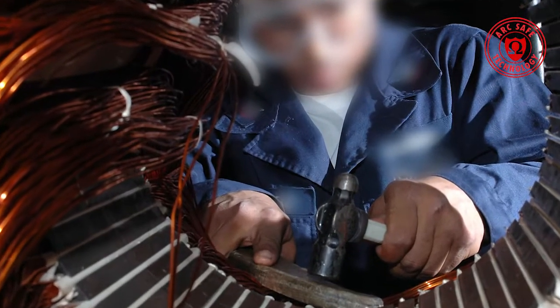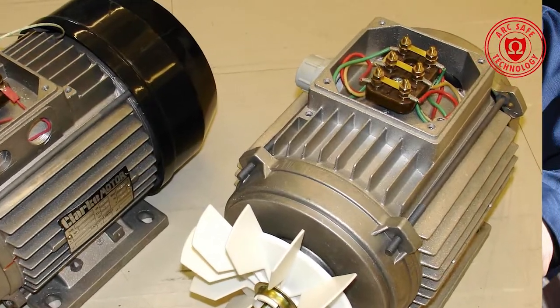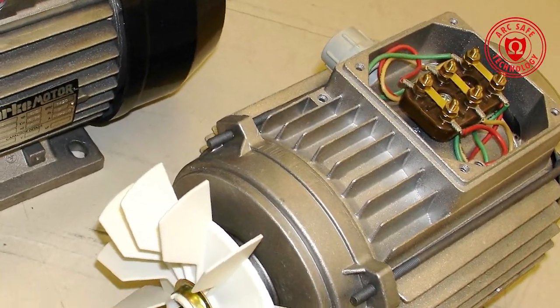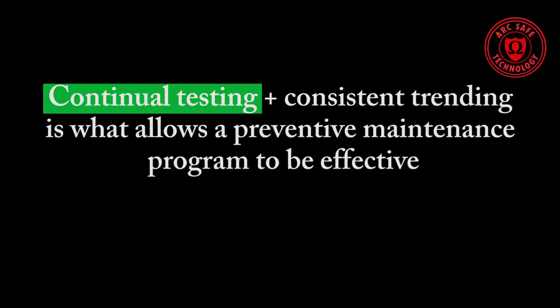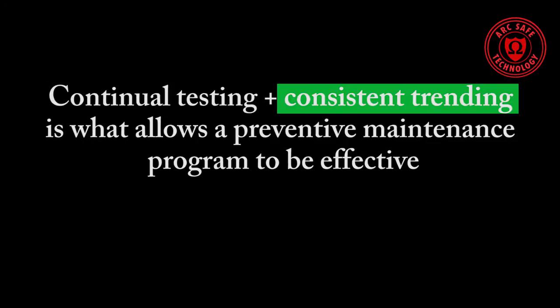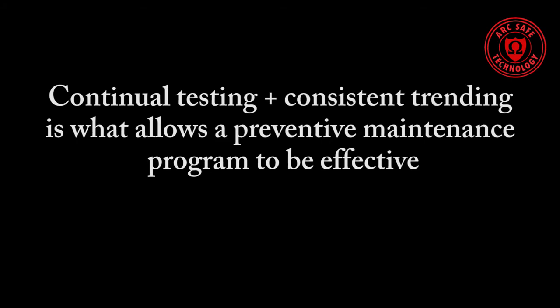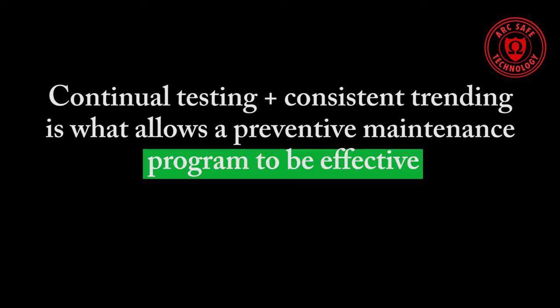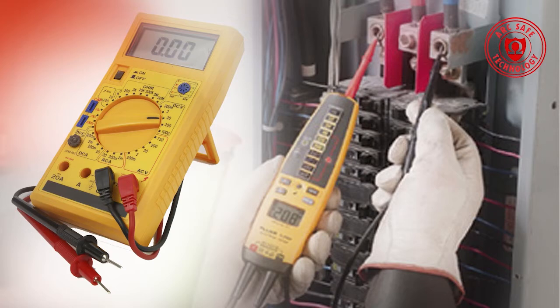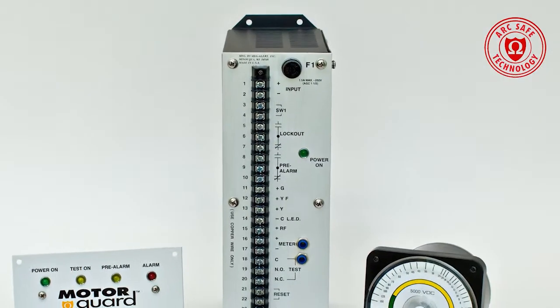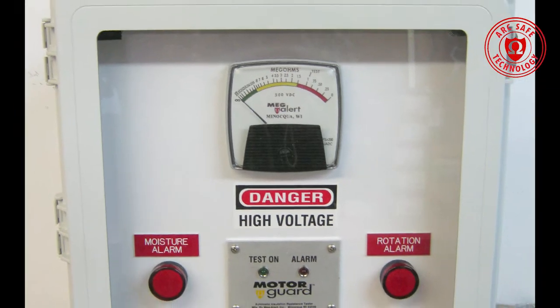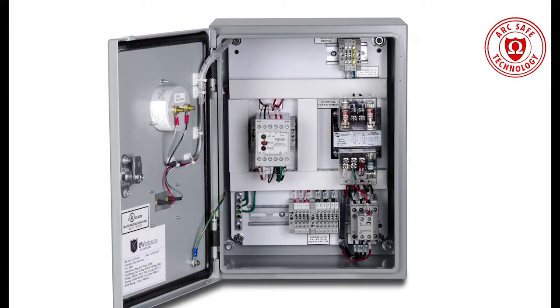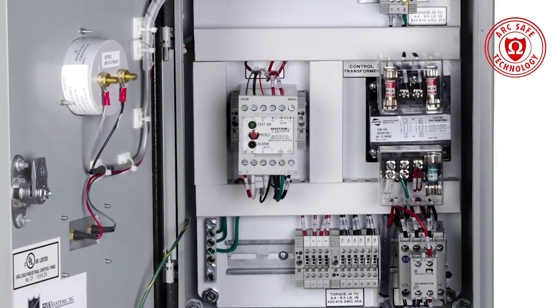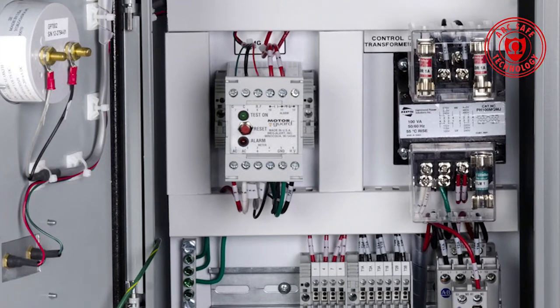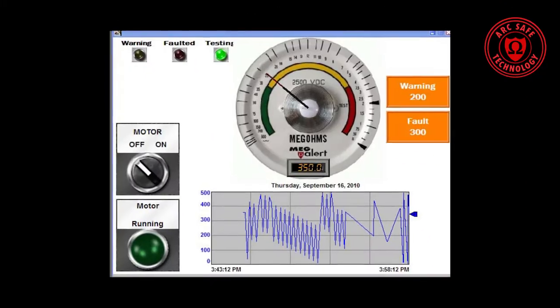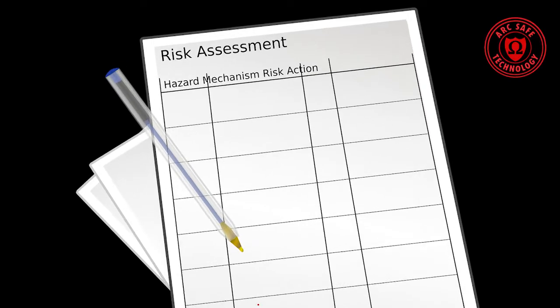Additionally, these critical pieces of equipment can then be reconditioned at less than half the time and expense of a complete rewind. Continual testing, followed by consistent trending, is what allows a preventive maintenance program to be effective. Unlike hand megohm testers, MegAlert units have the ability to trend data over time, which allows your maintenance supervisors to schedule preventive maintenance appropriately and keep critical equipment operational. MegAlert provides valuable data for more effective preventive maintenance scheduling.